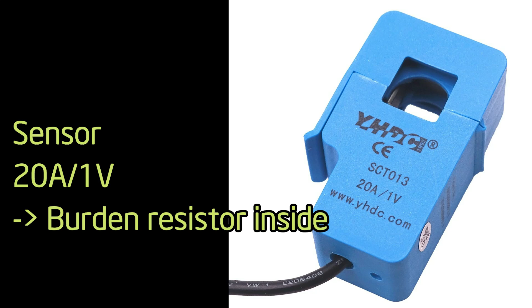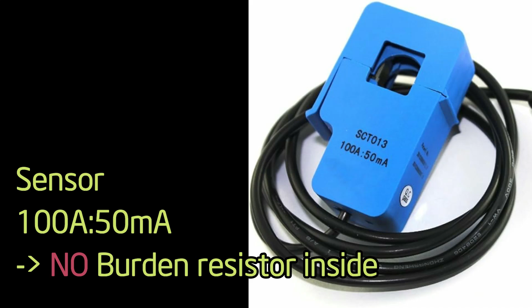For example, this kind of sensor with specification 20 amps per 1 volt will have a burden resistor inside. Meanwhile, the sensor with specification 100 amps per 50 milliamps will have no burden resistor inside, so we have to install a burden resistor for it.